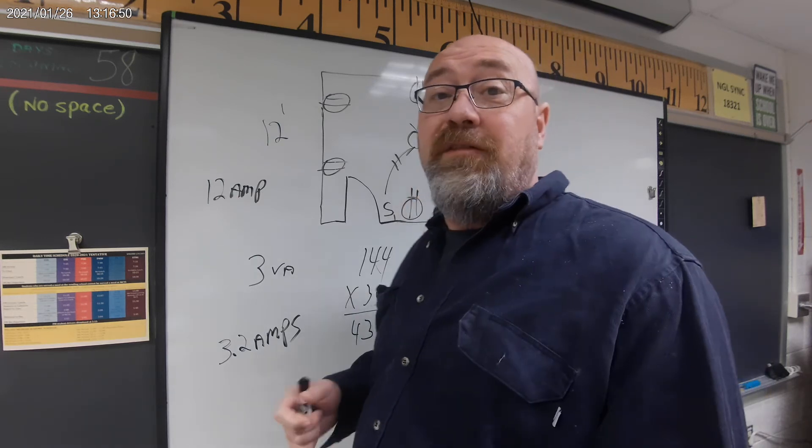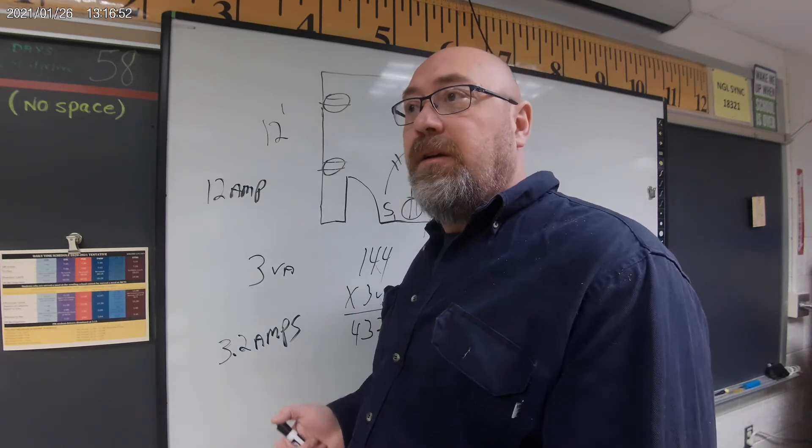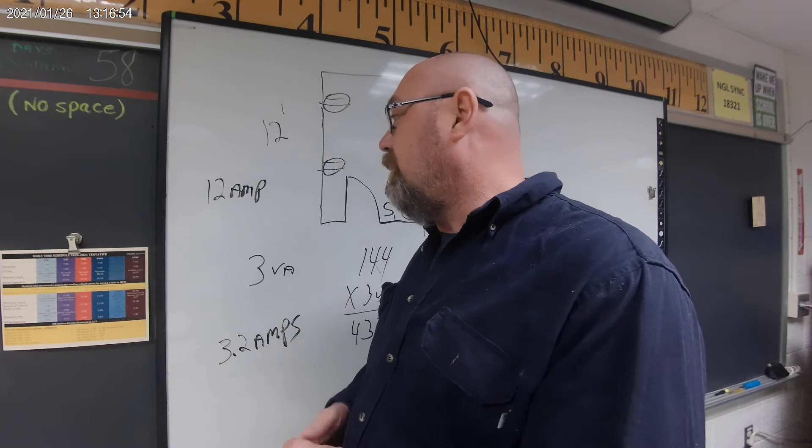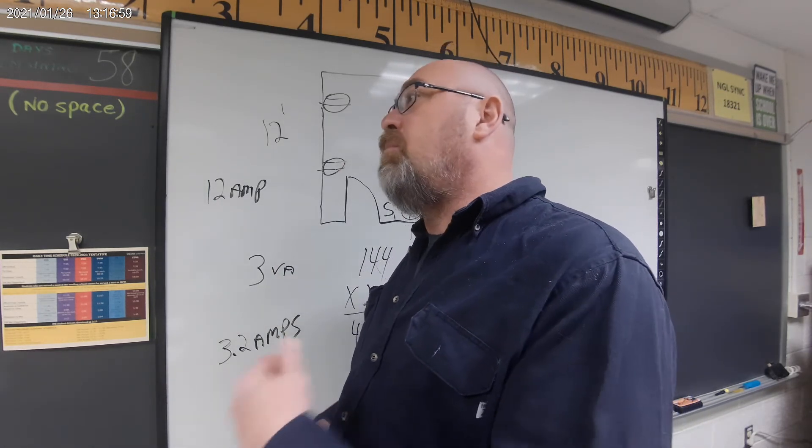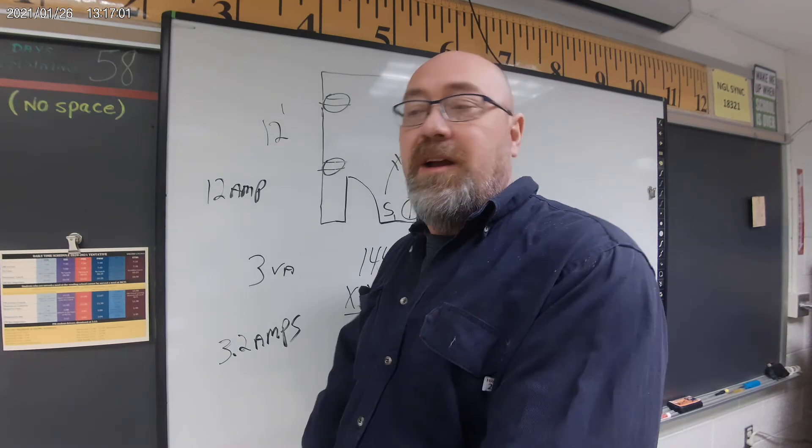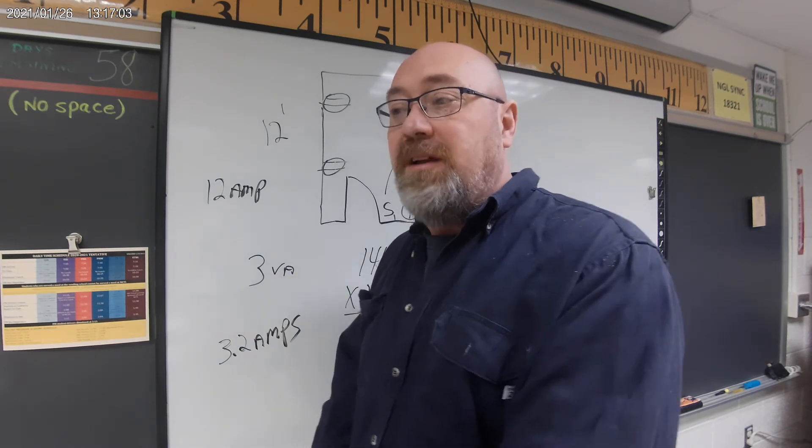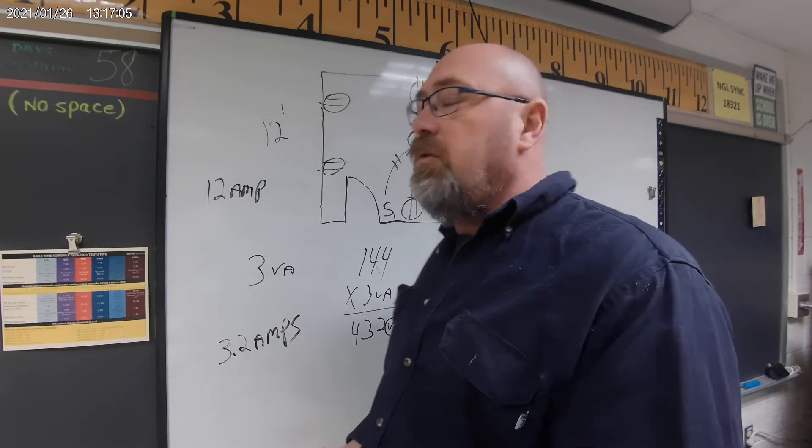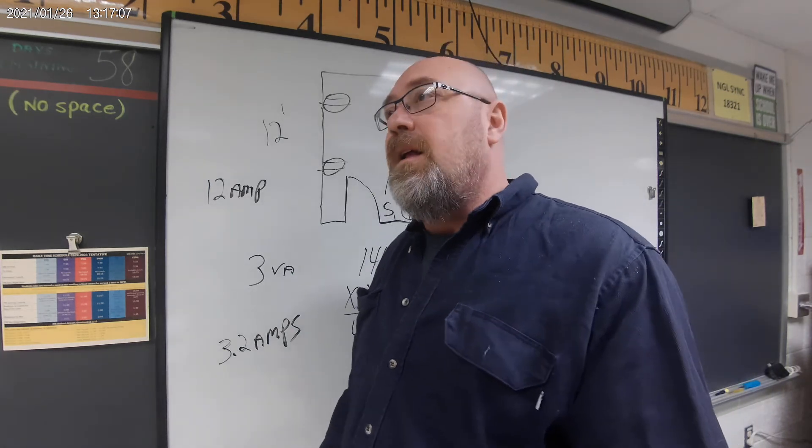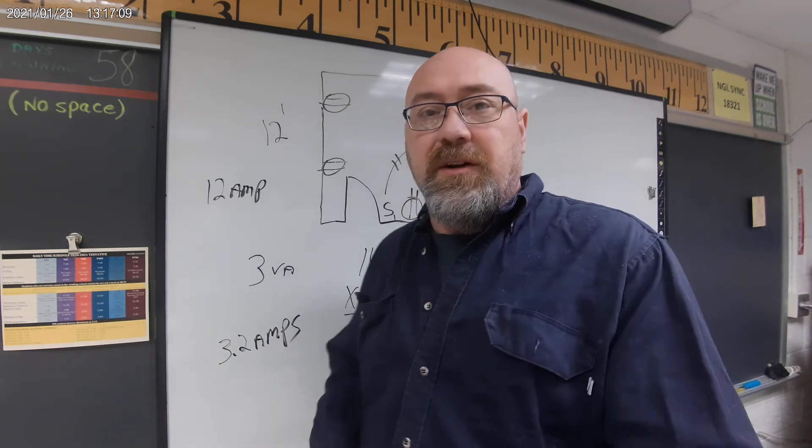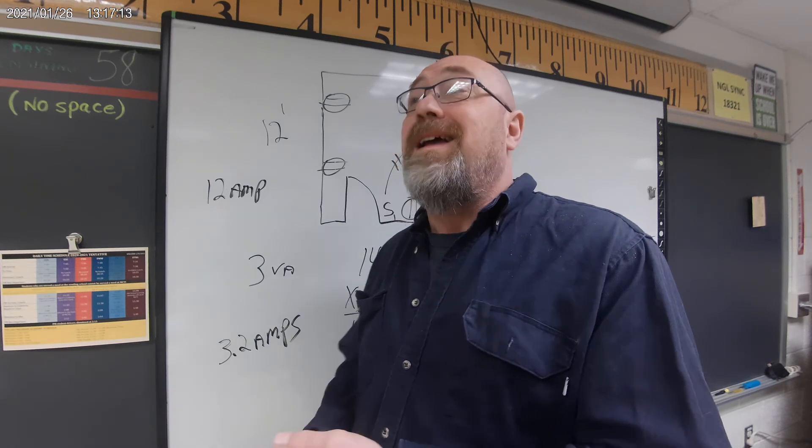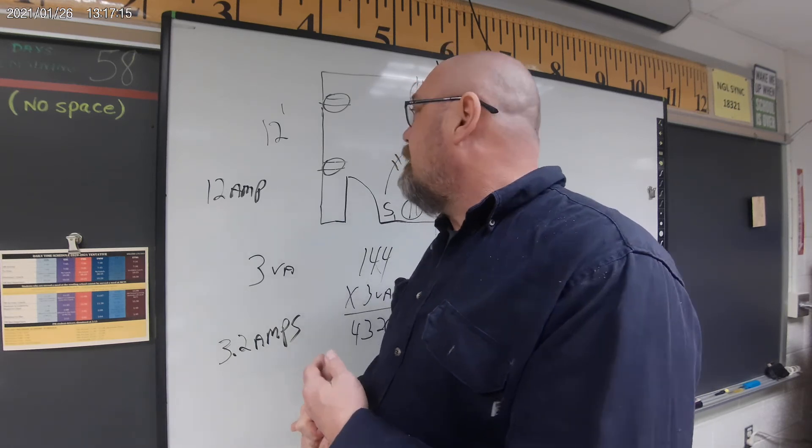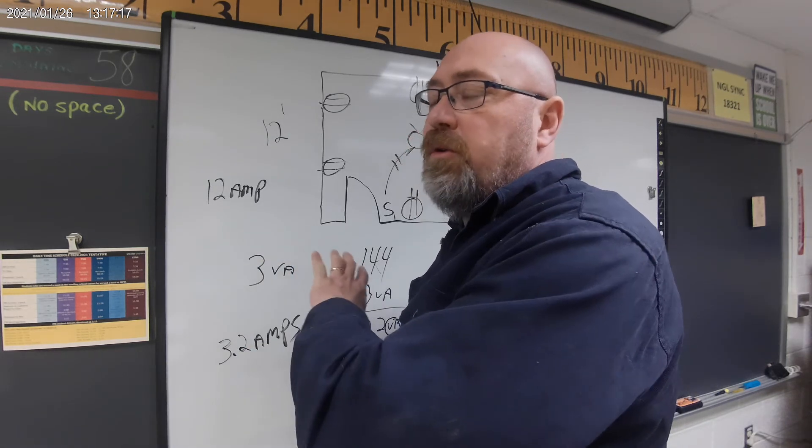It is totally legal and I'm only drawing seven of the 12 amps, so it is within more than enough of a range that I could put those two bedrooms on the same circuit. The reason we do that is for cost. If I have to add another circuit, that's another breaker, another home run from the panel box, and also labor.